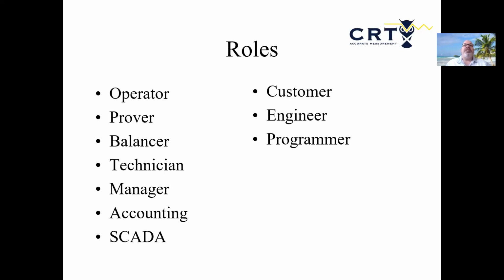We have to have an understanding of not only instrumentation and communications, but you need to understand basic measurement in general to make sure you're selecting the proper tables, K factors and meter factors, and how you're handling equilibrium vapor pressure, and a lot of other functions specific to a flow computer that aren't in a PLC or an IT system.